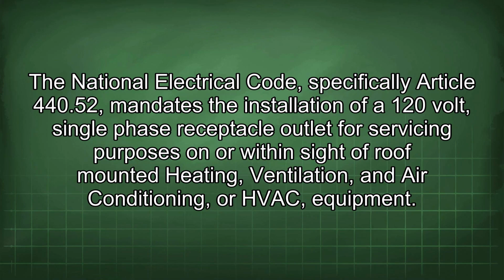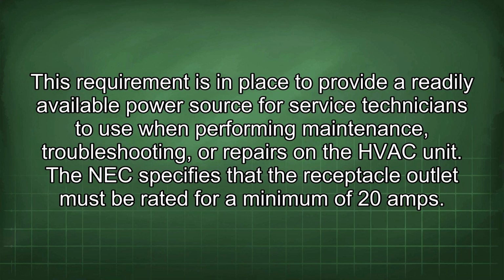The National Electrical Code, specifically Article 440.52, mandates the installation of a 120-volt single-phase receptacle outlet for servicing purposes on or within sight of roof-mounted heating, ventilation, and air conditioning, or HVAC, equipment. This requirement is in place to provide a readily available power source for service technicians to use when performing maintenance, troubleshooting, or repairs on the HVAC unit.